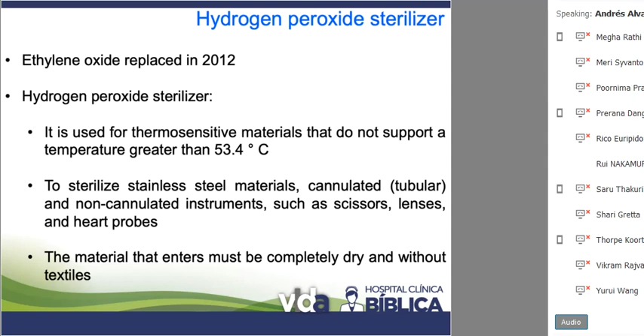In this case, this equipment, the hydrogen peroxide sterilizer, is used for thermosensitive materials that do not support a temperature greater than 53.4 degrees Celsius. It is used to sterilize stainless steel materials, cannulated and non-cannulated instruments, such as scissors, lenses, and heart probes. And one important thing is that the material that enters must be completely dry and without textiles.